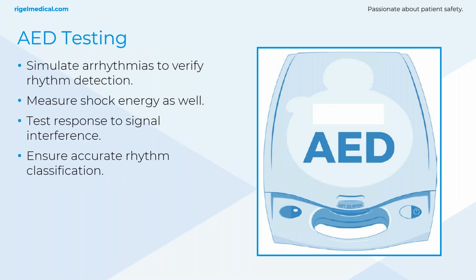And a little bit more about AED testing. This is the device that's going to be used during those real world scenarios, out in the field, in public. And what we want to do is make sure that testing an AED isn't just shining a light and saying, oh well, it powers on, it lights up, there's a battery, it's all good. These devices also have algorithms for measurement that need to work with accuracy. You make sure that those rhythms being measured are accurate. So we're making sure that those are tested as well.